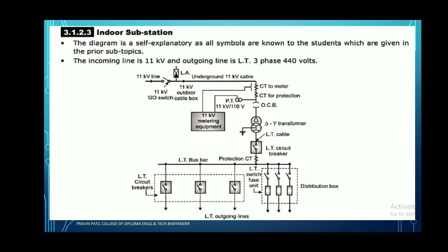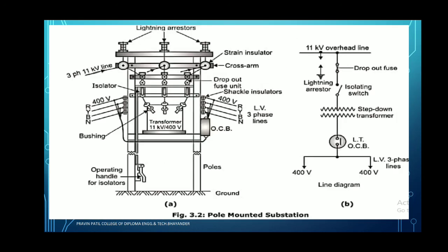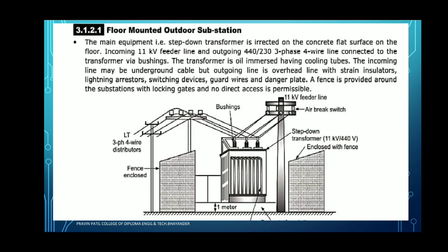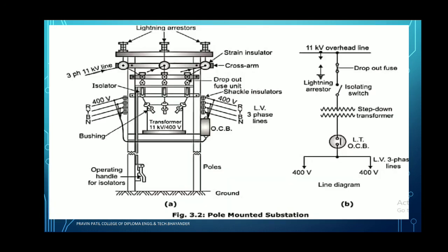We have to see again the diagram representation of the device. This is the pole mounted substation and this one is the floor mounted substation. Here we have to observe that the transformer has some distance from the ground, and in between, the operating handle for the isolator is connected. Some distance is maintained from ground level up to a certain level, and up to that level the transformer is connected.